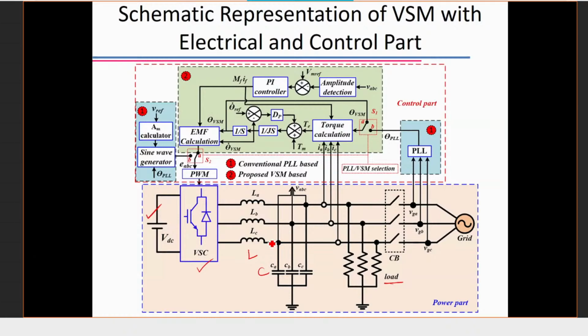In this virtual synchronous machine, we have provided a feature to operate in remote mode, that is, islanded mode, so we preferred the LC filter. This is the control part of the whole virtual synchronous machine: according to the voltage and current sensed from the point of common coupling, and the grid voltage we sense, the conventional mechanism works. Whereas in the virtual synchronous machine, three sensors are sufficient -- that's another attractive feature of VSM. With the help of three current signals, the whole VSM can be operated.